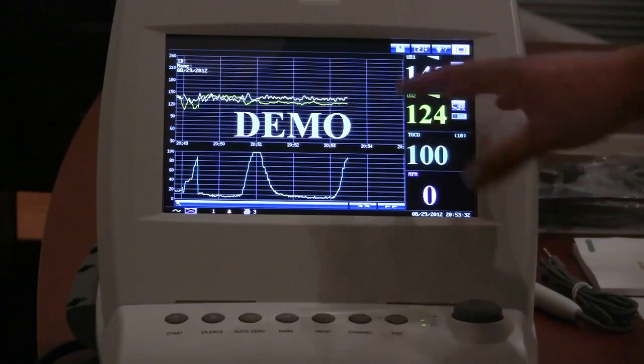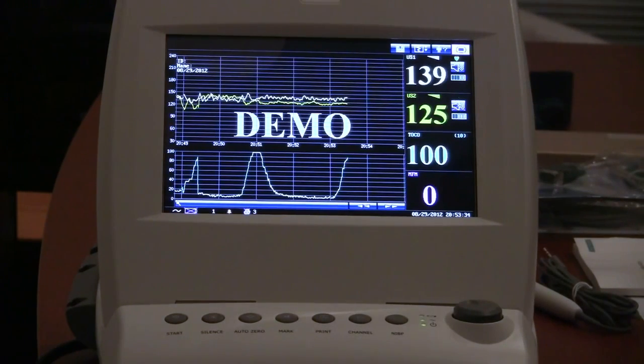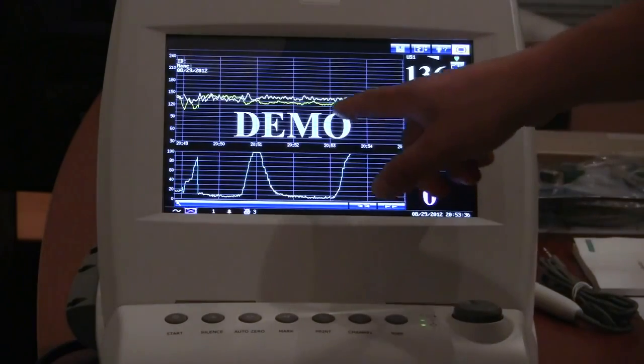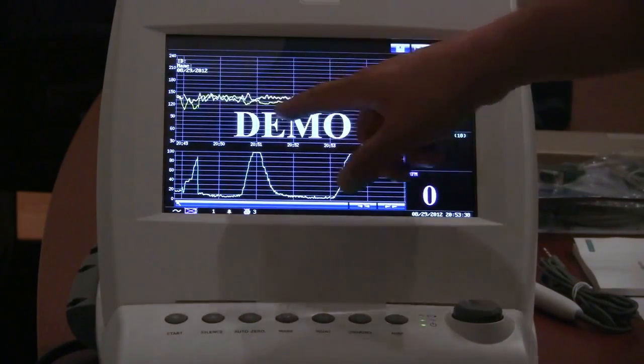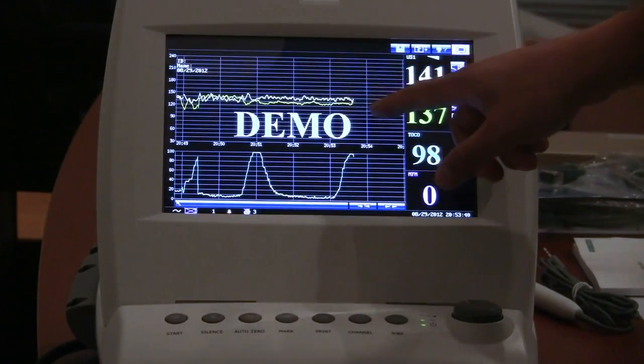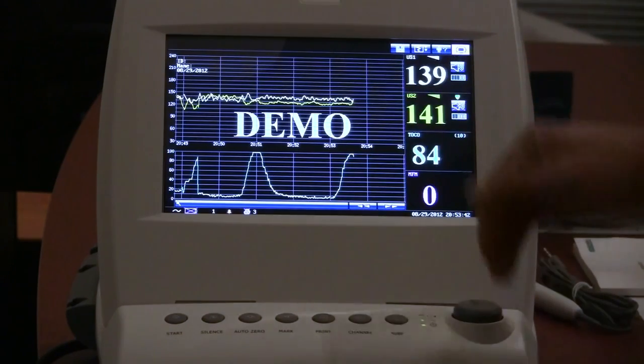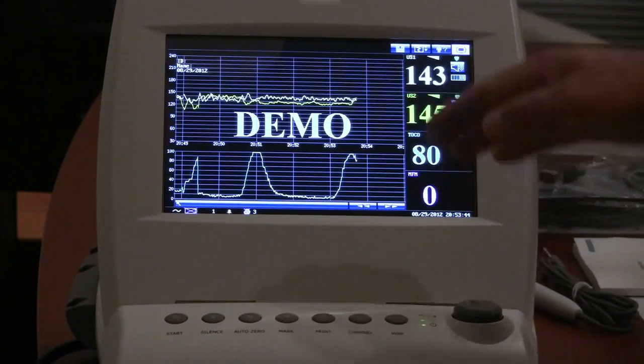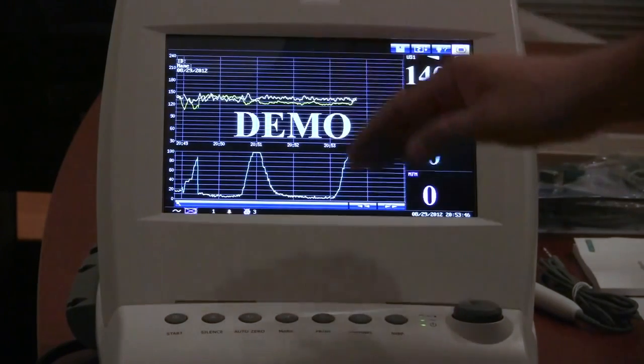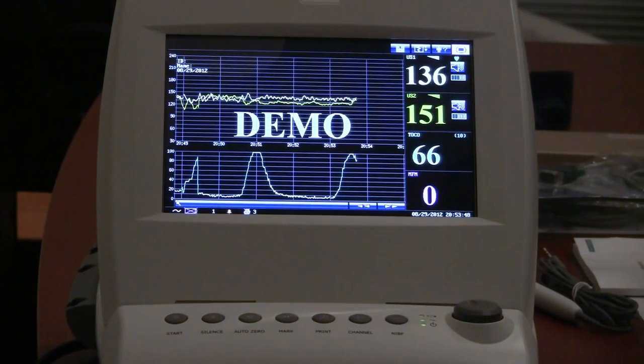There's a couple different ways that you can configure this unit based upon user preference. Right now we've got it set up where the tracings for fetal heart rate 1, or baby 1, and baby 2 will actually overlap. You can set this to offset it as well so that one will be lower than the other one. Again, that's a user preference. I find that most practitioners would like them to overlap so that if they glance at the screen they don't see something that would appear to be out of whack because the lines are offset.